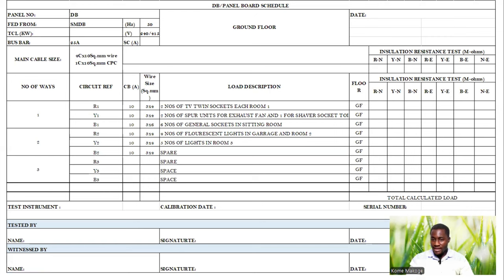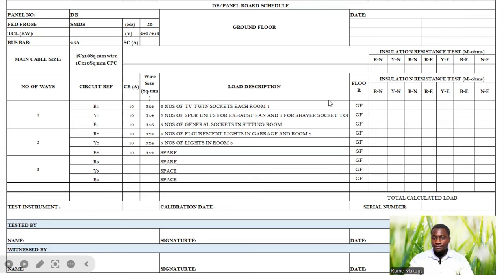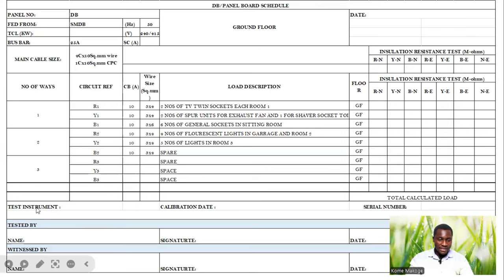We now move to the outgoing cables. We perform the same test for the different wires — R1, Y1, B1, and then R2 and Y2; the rest will be spare. We perform the insulation resistance test measured in megaohms, performing the test between red phase and neutral for R1, and recording results corresponding to the different circuits. We also record the test instrument details, including the calibration date and serial number.